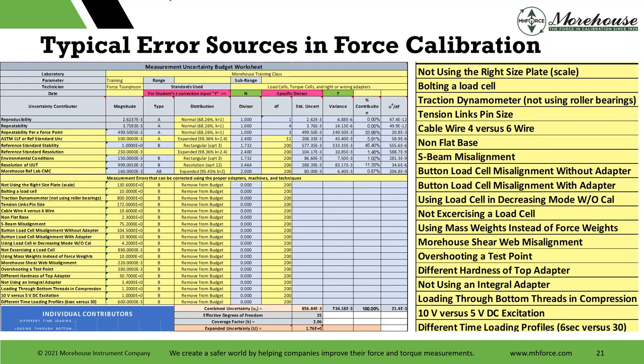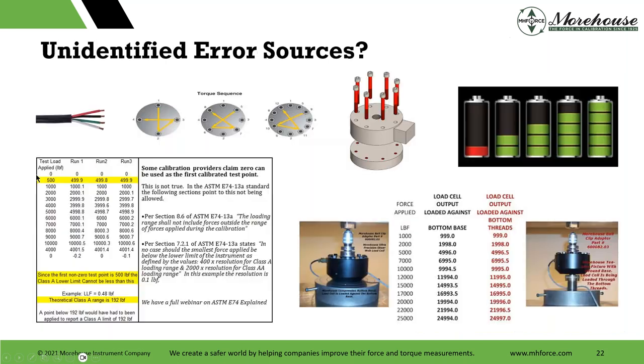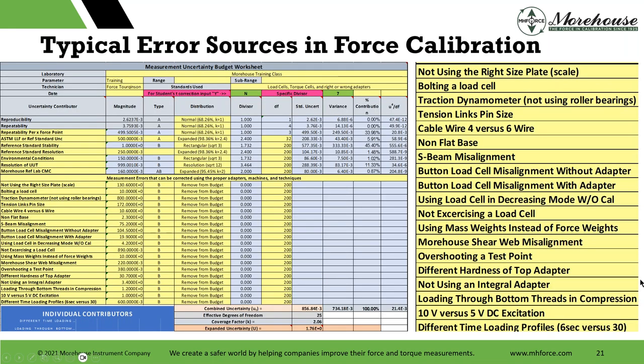But if we look at these errors, I created this when I train in person. I created this uncertainty sheet here. And basically you have a standard budget up here. This is our standard budget for uncertainties, you know, reproducibility, repeatability, usually ASTM, lower limit factor. And then all of these things below add a lot of error, and you can see what type of additional uncertainty or error they add when you select them.